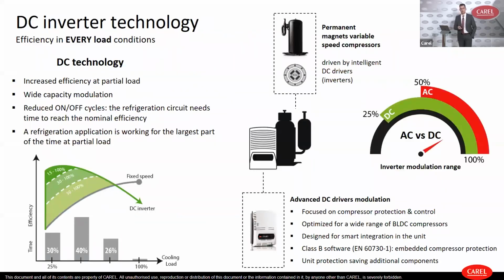Let's start with a quick overview of our DC inverter technology. With DC inverter technology, we speak about DC inverter drives that are designed by CAREL in order to manage permanent magnet, variable speed compressors. The main feature of these compressors is the possibility to have a very wide range of modulation. And by the use of this DC inverter, we can increase and keep high the efficiency of the compressor, but also of the entire system at the end, even at partial load. So the COP of these compressors managed by DC inverter will be high at all the operating conditions of the unit.